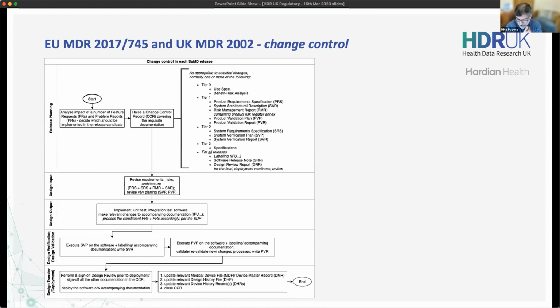So maybe to meet that, you've added some training data to an AI deep learning model. So now you need to test with that training data, the various set points in it. Can you meet the accuracy? Can you draw the ROC curve? And are you still going to achieve or be superior to the accuracy spec you've set? So that's a re-verification. Tier 1 change is a potential revalidation.